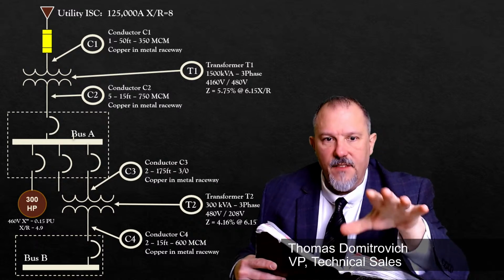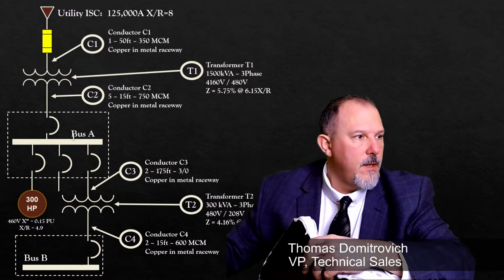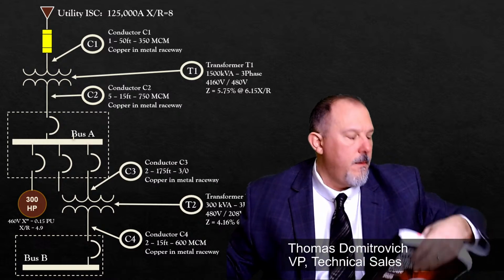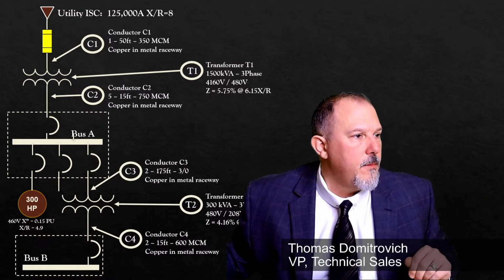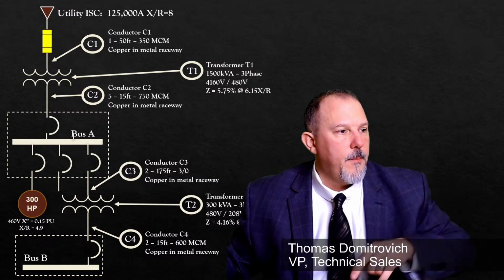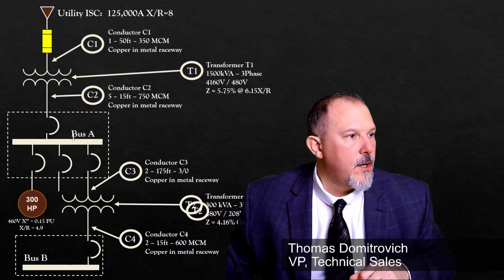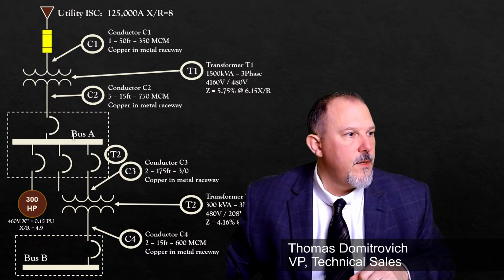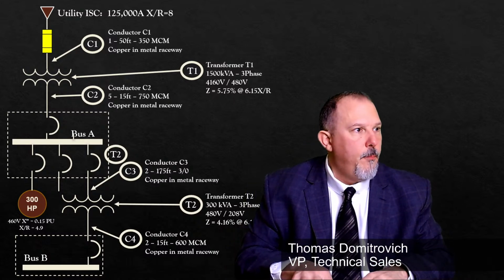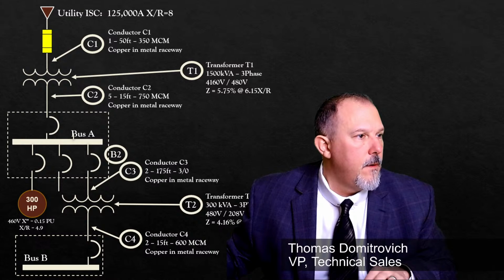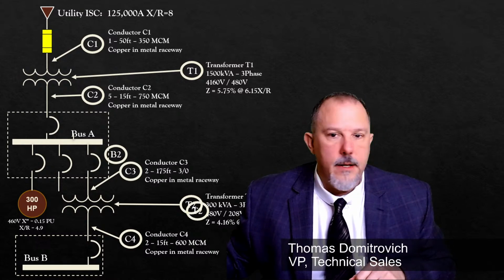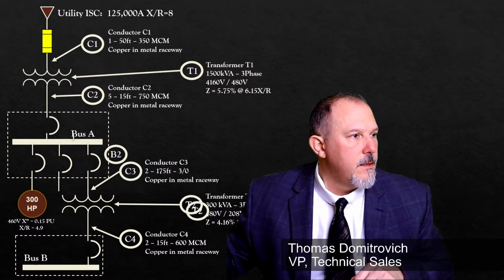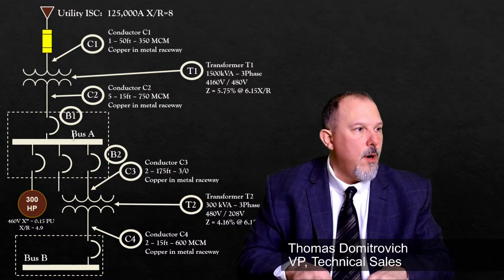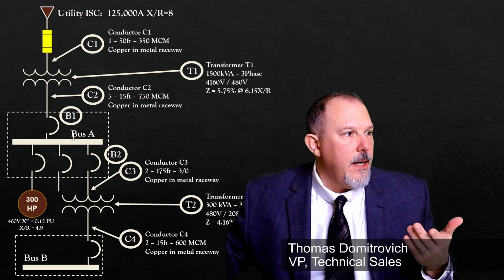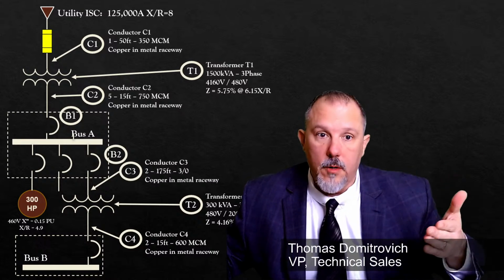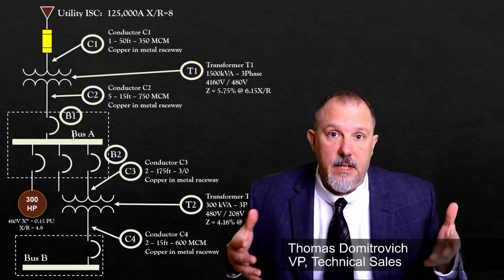So here's what happens. If I have a miscoordination between, I'm going to copy. I'm going to call this breaker 2. And I'm going to call this breaker 1. So breaker 1 is the main in this bus A, this switchboard, because we've already identified it's a 2000 amp switchboard.